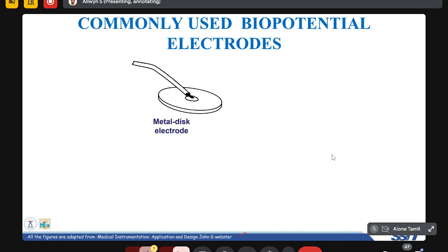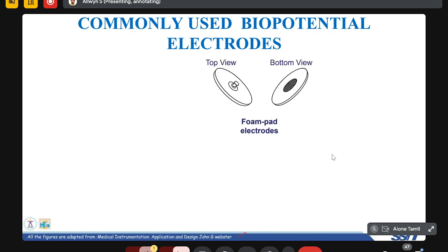And the next one is the metal disc electrode. It's a small disc made of stainless steel or platinum or gold coated, usually used to measure EMG or EEG. Yes, so this can be easily integrated in a skull cap to measure the EEG. And another one is the disposable foam pad electrode. Yeah, this we have seen regularly. It's made up of sticky foam. In the middle this is AgCl electrode, and in between we have electrolyte. This is much cheaper and easy to use.